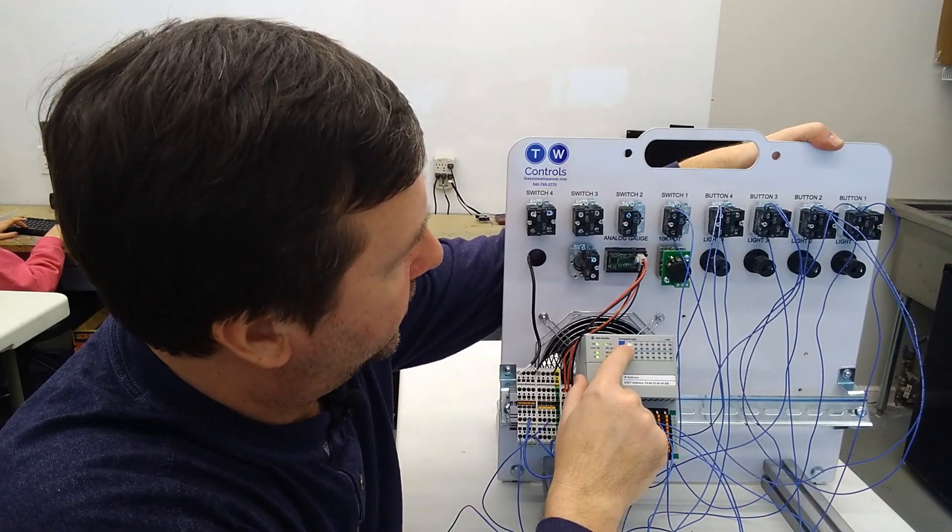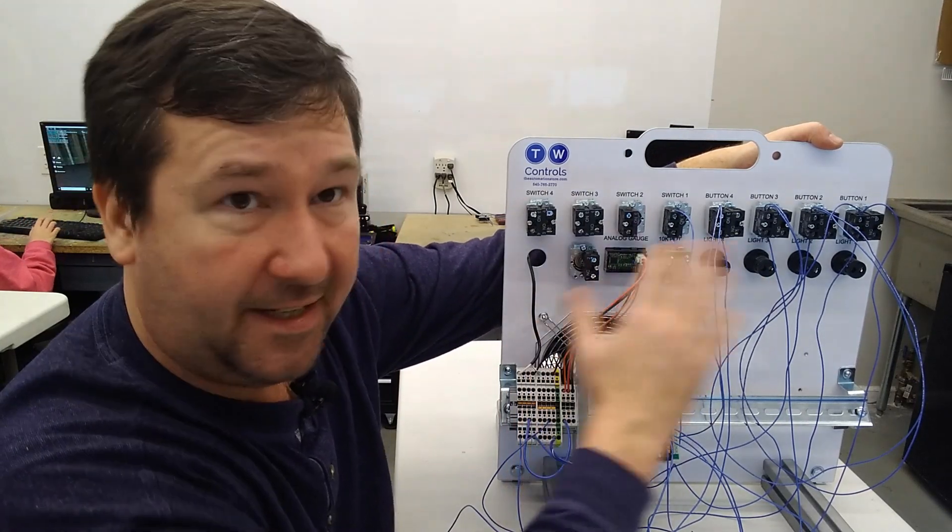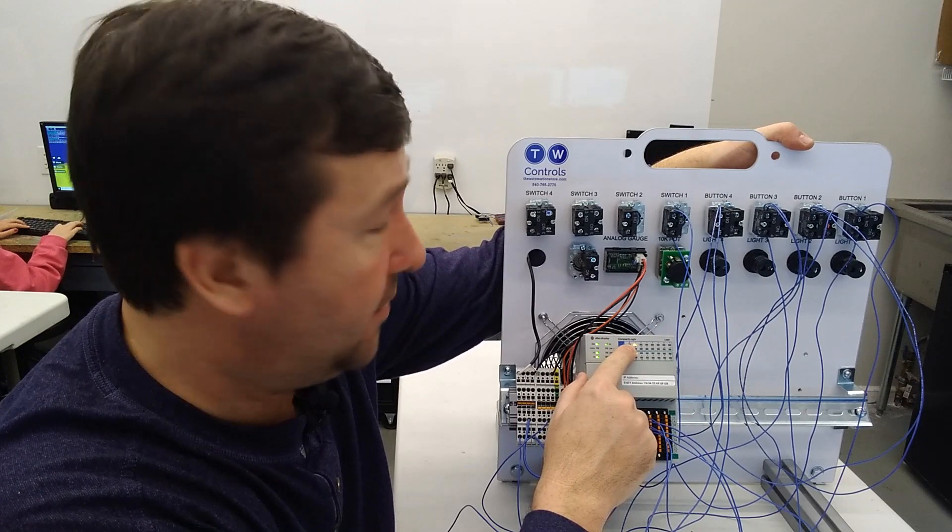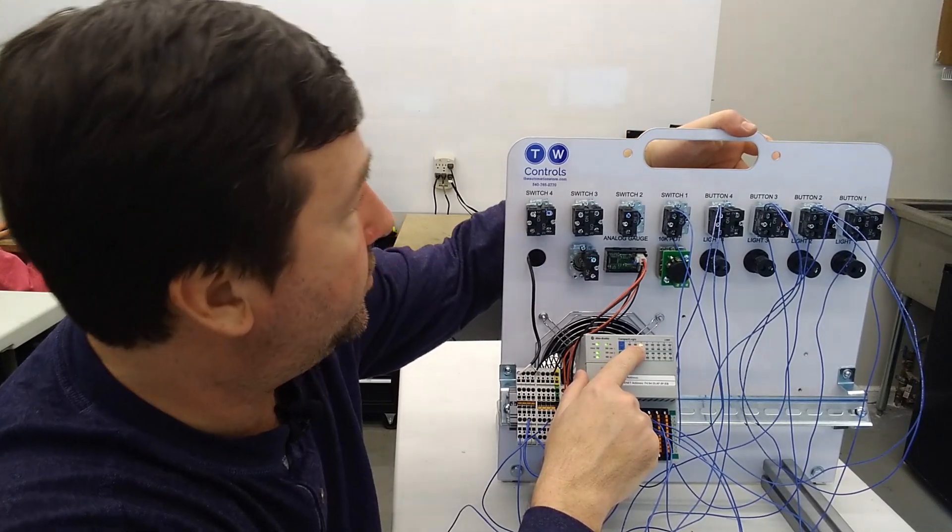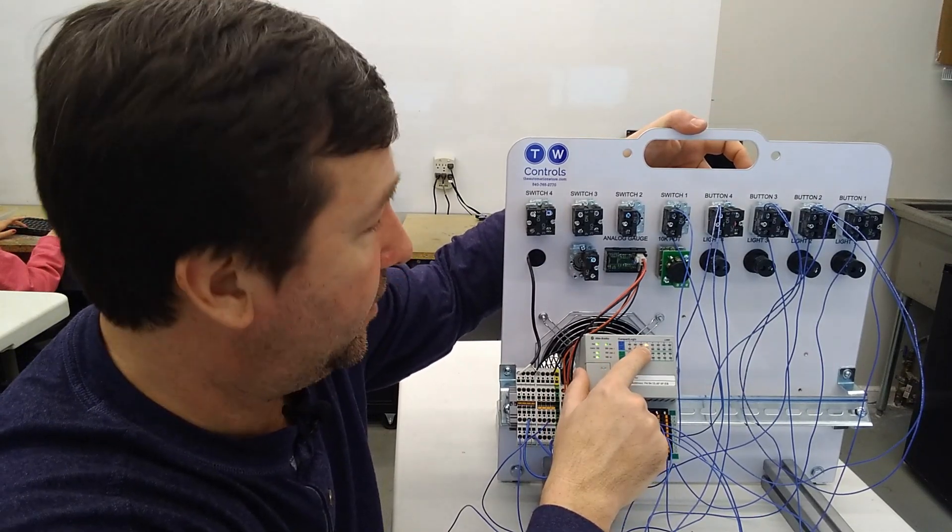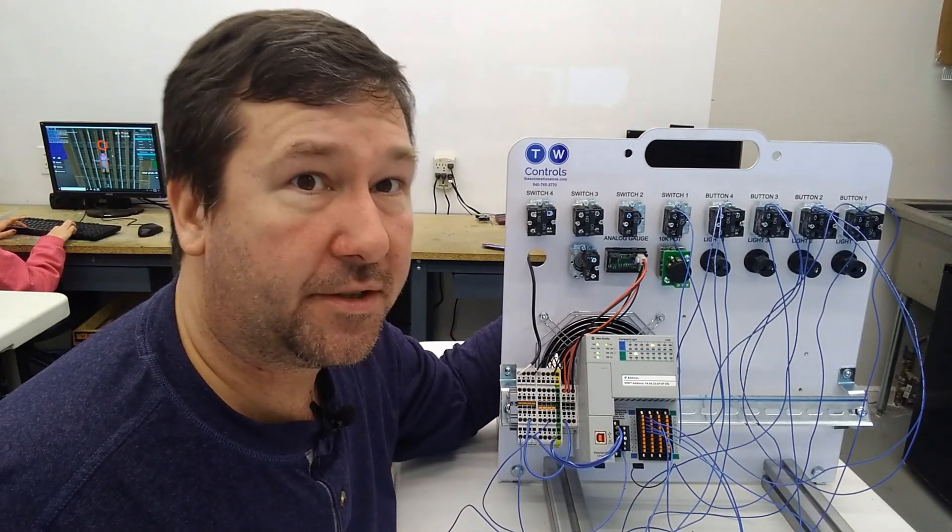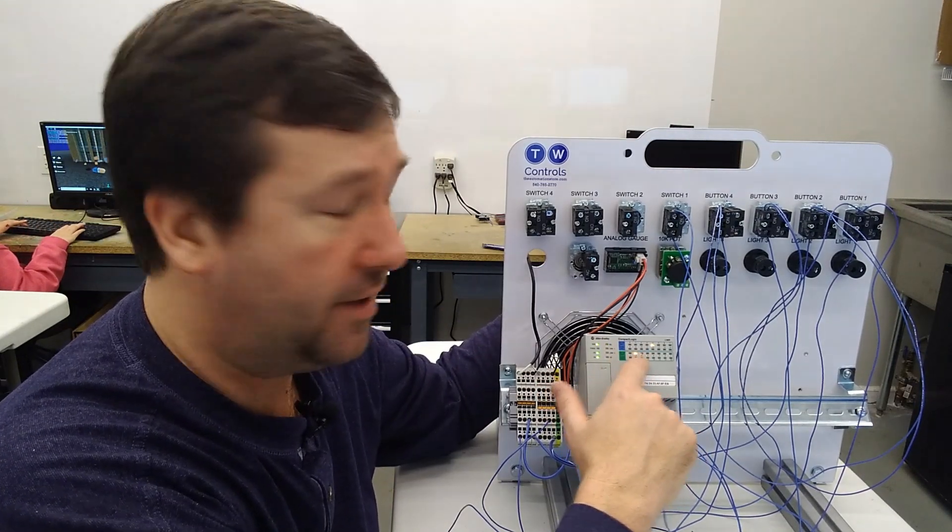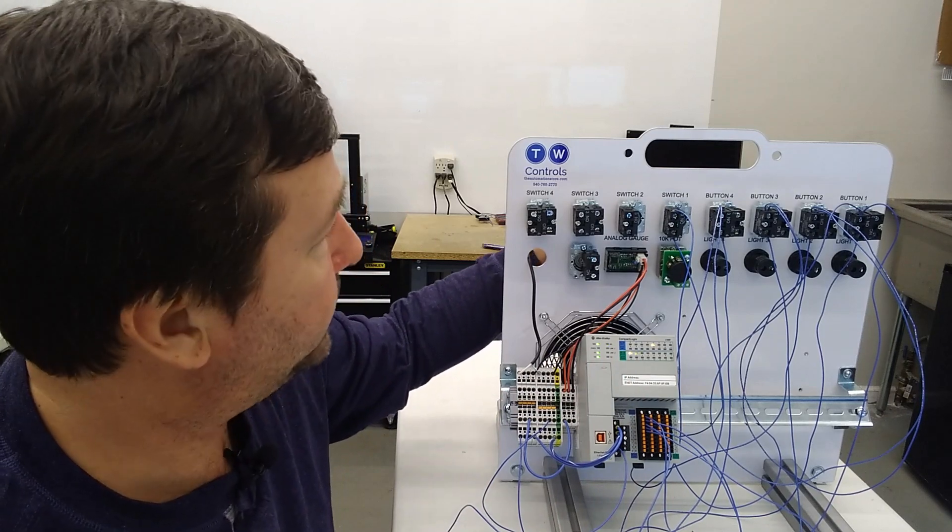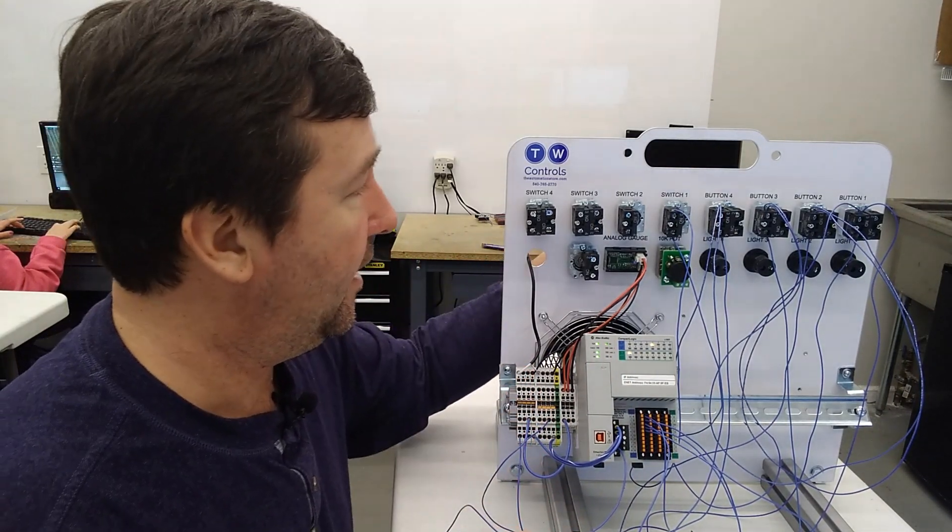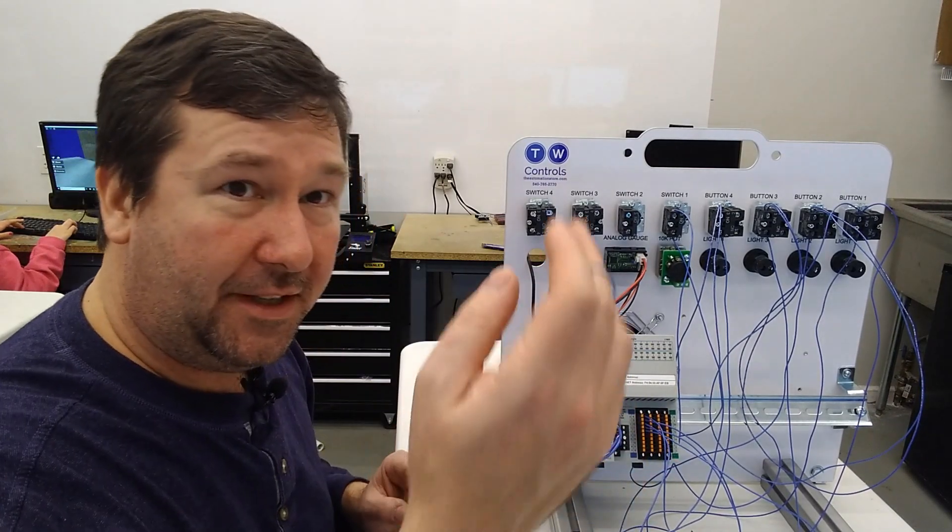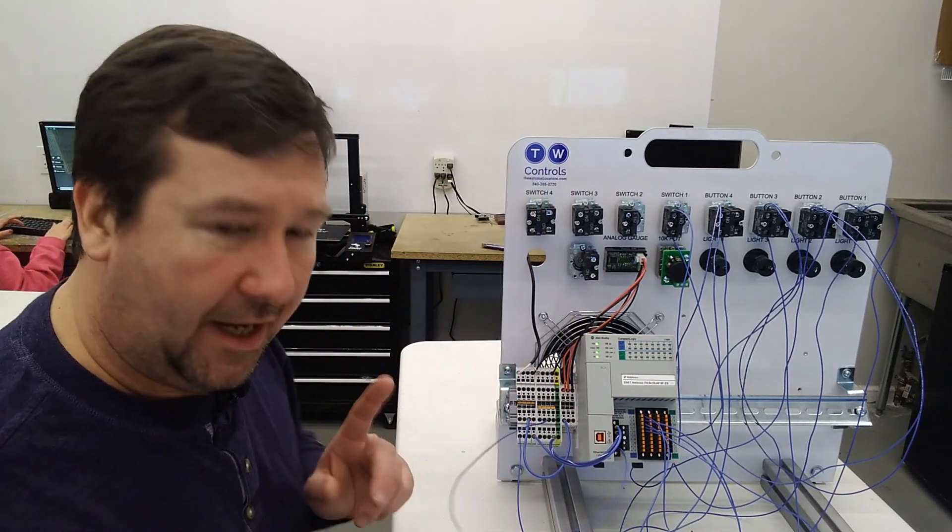Button one is going to turn on input zero. And we'd already tested that, but it's good to test it again, since we added some more wires. Button two is going to turn on input one. Button three is going to turn on input two. Button four is going to turn on input three. And switch one is going to turn on input four. You'll see a sequence going across here. Once switch one is on, like I said, just ignore the outputs for now. If yours is not doing that, take the time just to trace out that wiring and figure out what the problem is. Don't move any further.